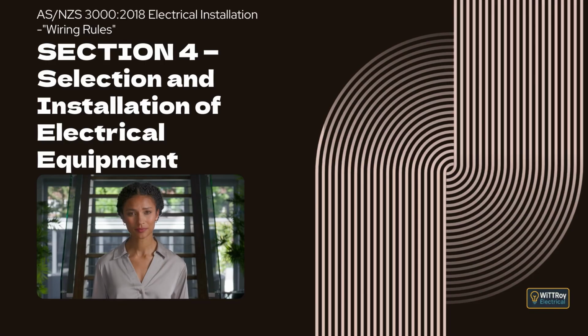Clause 4.12.7 Neutral continuity. This clause explains that electricity converters, particularly static converters such as UPS systems, must be arranged so the neutral conductor to the load is not interrupted during bypass or maintenance switching.